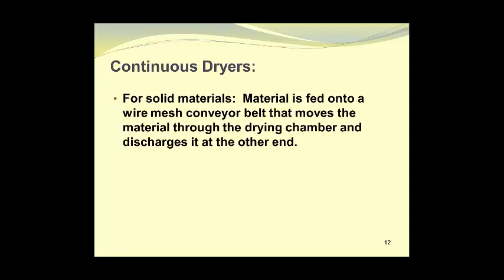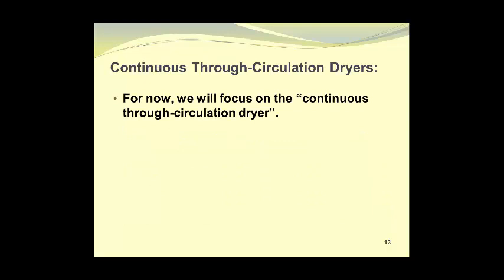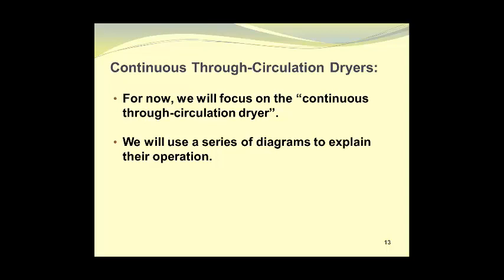Now let's take a look at continuous dryers. For solid materials, the material is fed onto a wire mesh conveyor belt that moves the material through the drying chamber and discharges it at the other end. For slurries or solutions, material is pumped into the drying chamber through a spray nozzle assembly into hot air and is separated from the hot air stream that conveys it. For now, we will focus on the continuous through-circulation dryer, using a series of diagrams to explain their operation.